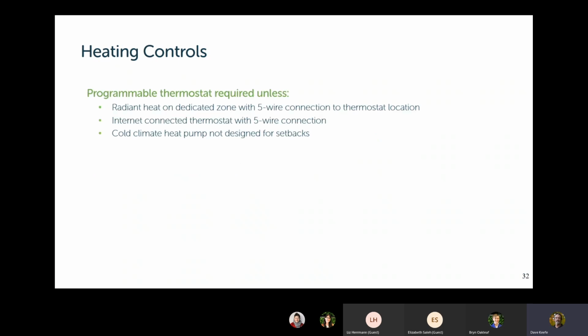There are also requirements over controls. You're required to have a programmable thermostat unless you have a radiant heat and you have a 5-wire connection. In other words, you got good wiring in place, so as to provide lots of flexibility for how that's controlled in the future. If you have an internet connected thermostat with a 5-wire connection, you do not need to be programmable. Although I'd note that I'm not sure that an internet connected thermostat which is not programmable even exists. And if you are doing a cold climate heat pump, they typically come with their own dedicated thermostats, and often they are not designed for setbacks, and setbacks are less useful and sometimes detrimental with heat pumps anyway. So lots of times the standard recommendation with heat pumps is set it and forget it. Don't do setbacks.